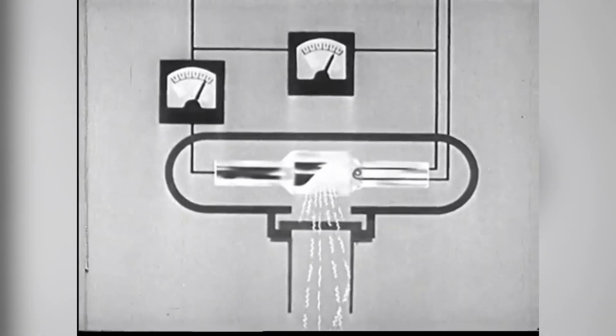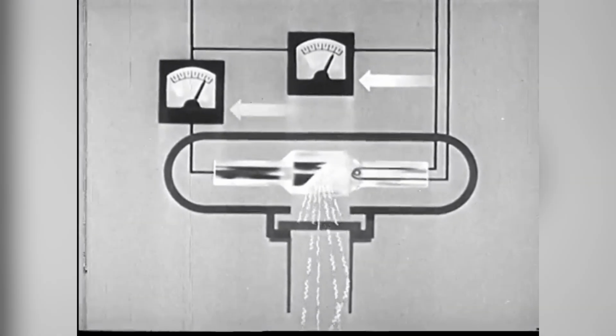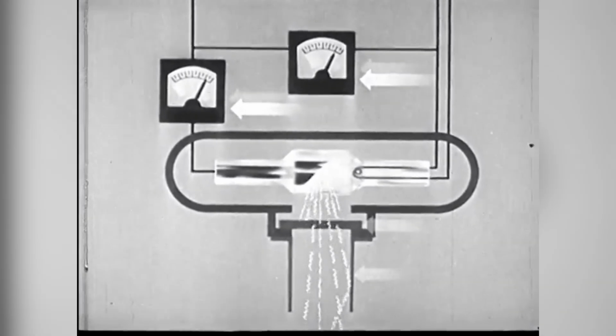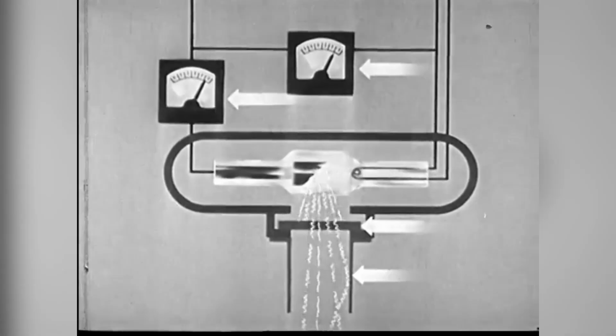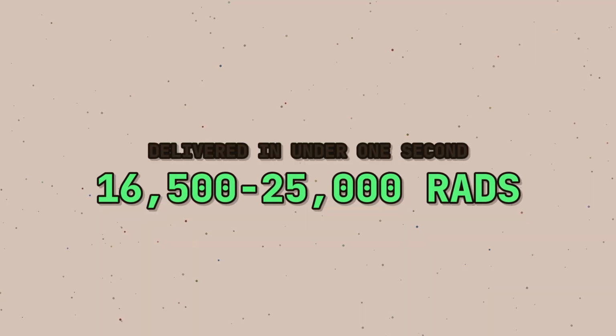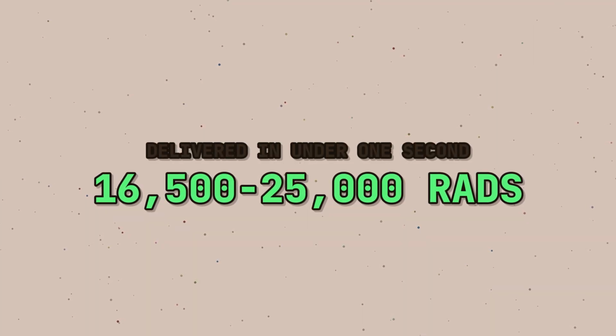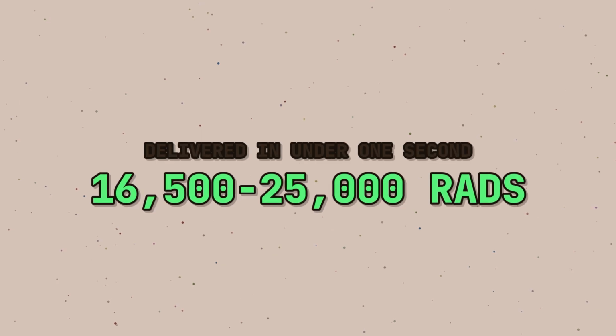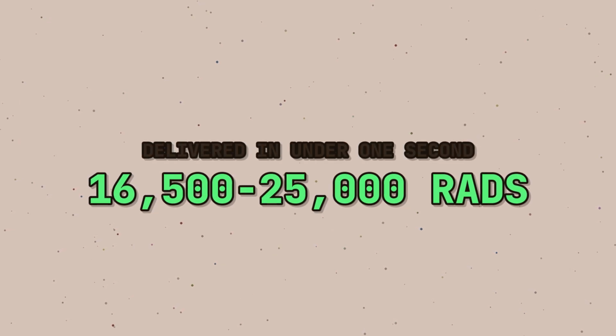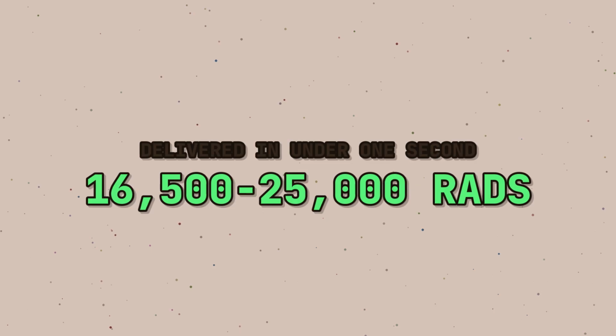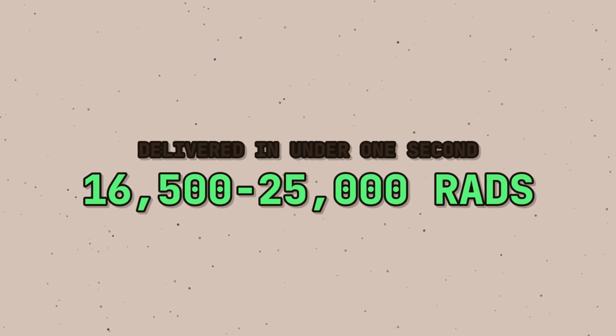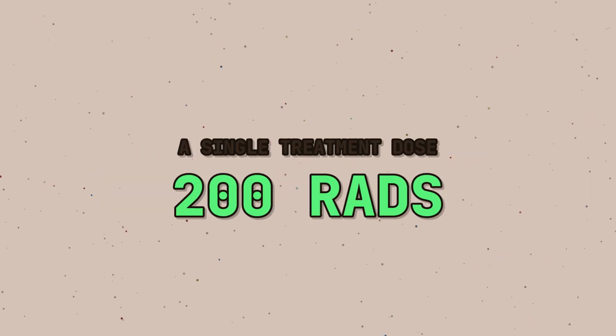for X-ray mode. Beam current for photon therapy is roughly 100 times that used for electron therapy, and the target and flattener meant to absorb it were no longer in the path. Simulations of the first Tyler accident later indicated doses of 16,500 to 25,000 rads in under 1 second across about 1 square centimeter. A single therapeutic dose in 1986 was in the region of 200 rads.